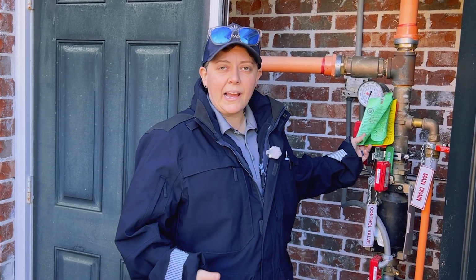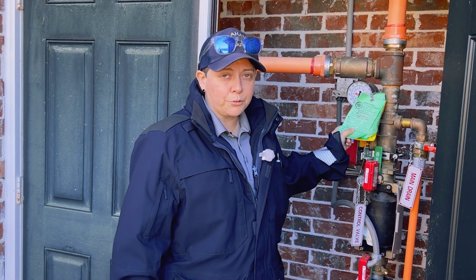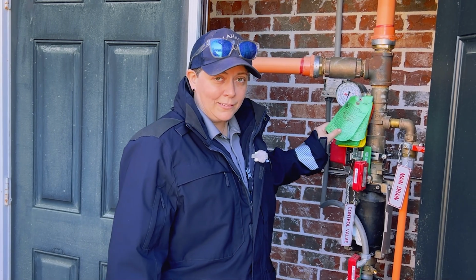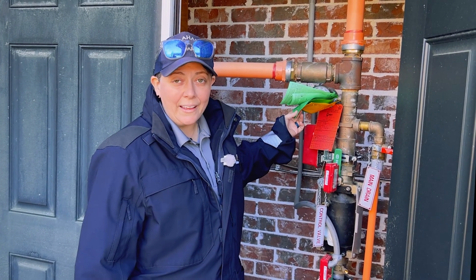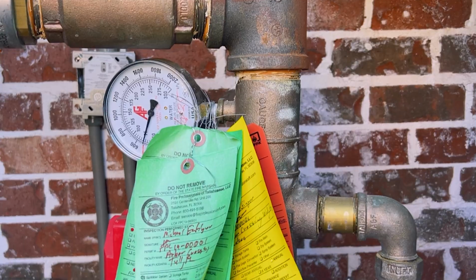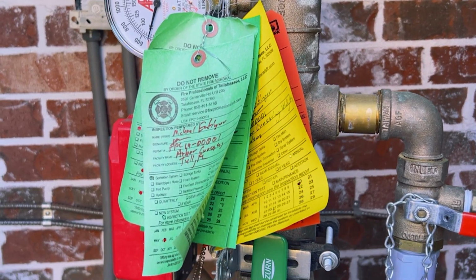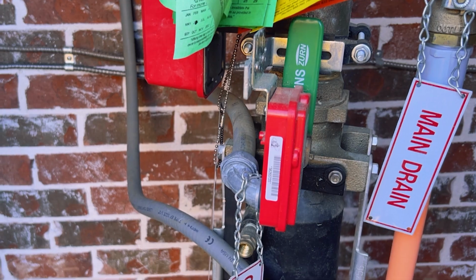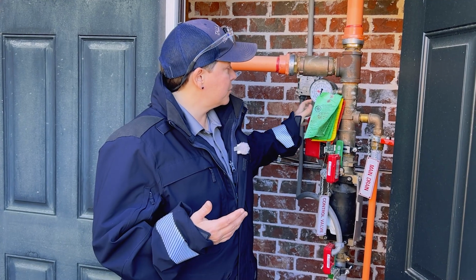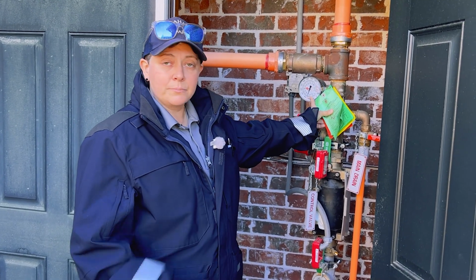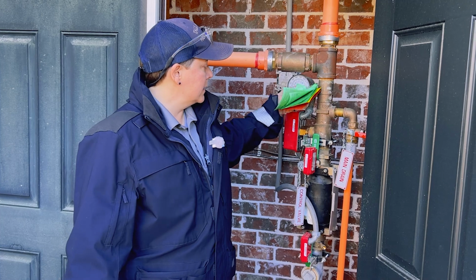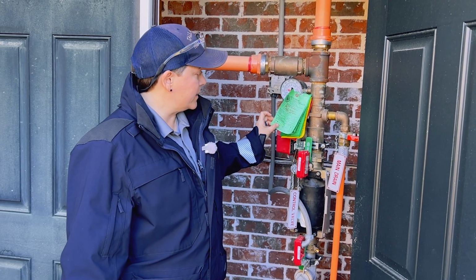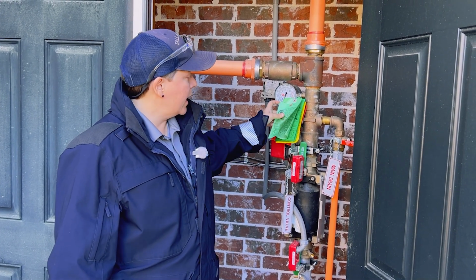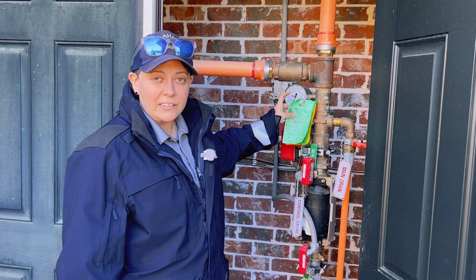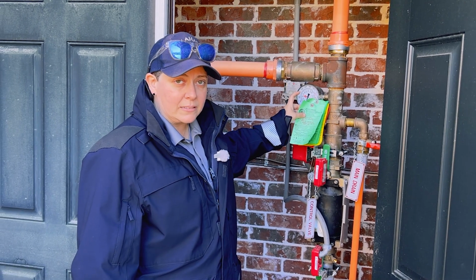So the three types of tags that you'll normally see on your riser or your sprinkler system is green, yellow, or red. And these are all ors, not ands. So green means good. That means that the system is in compliance. Everything is working as it should. And as an inspector, I'm also going to look at the pressure, make sure the pressure is where it needs to be. I'm also going to look at the date that they came out and make sure that this is a recognized company that actually inspects these systems.